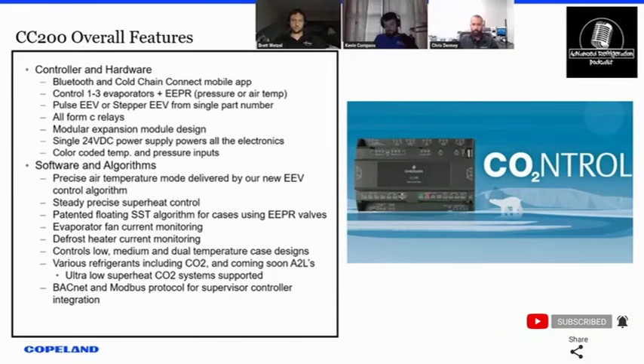I'll say the North American market is pretty heavy Sporlan Danfoss. Right now our approved valve list is heavy on Sporlan, but we're looking to add more Danfoss on the stepper valve side coming up. And then on the pulse valve side, we're good to go there for pretty much any 120 volt pulse valve, and then I don't come across too many 24 volt valves, but we do support 24s as well.